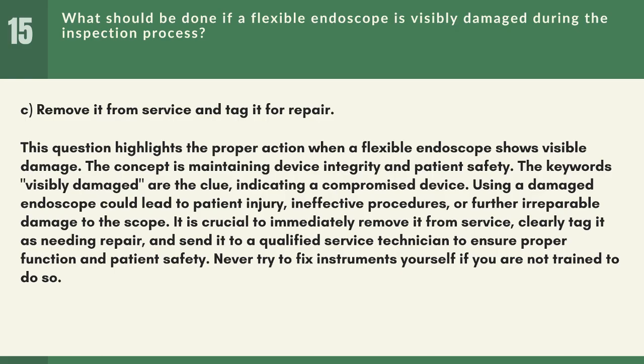This question highlights the proper action when a flexible endoscope shows visible damage. The concept is maintaining device integrity and patient safety. The keywords "visibly damaged" are the clue, indicating a compromised device. Using a damaged endoscope could lead to patient injury, ineffective procedures, or further irreparable damage to the scope. It is crucial to immediately remove it from service, clearly tag it as needing repair, and send it to a qualified service technician to ensure proper function and patient safety. Never try to fix instruments yourself if you are not trained to do so.